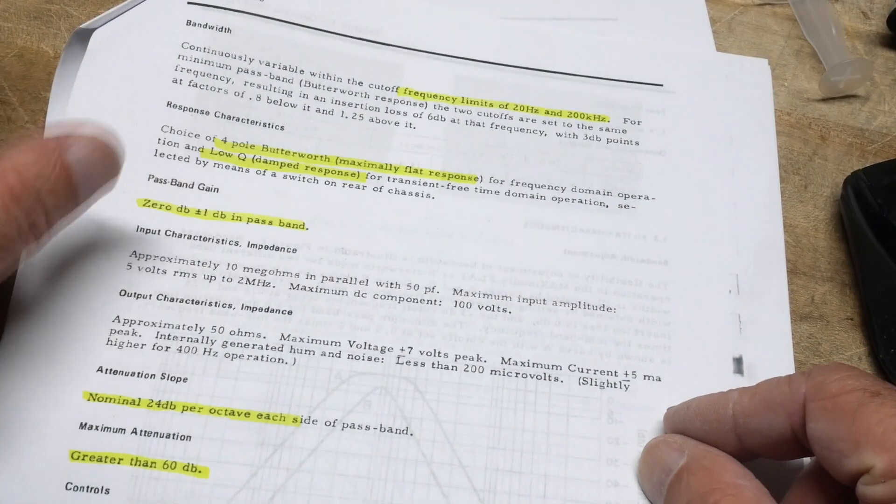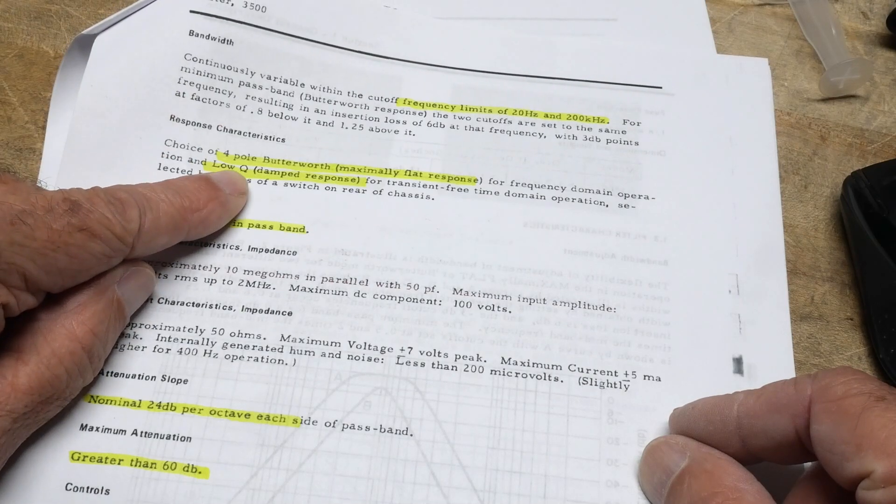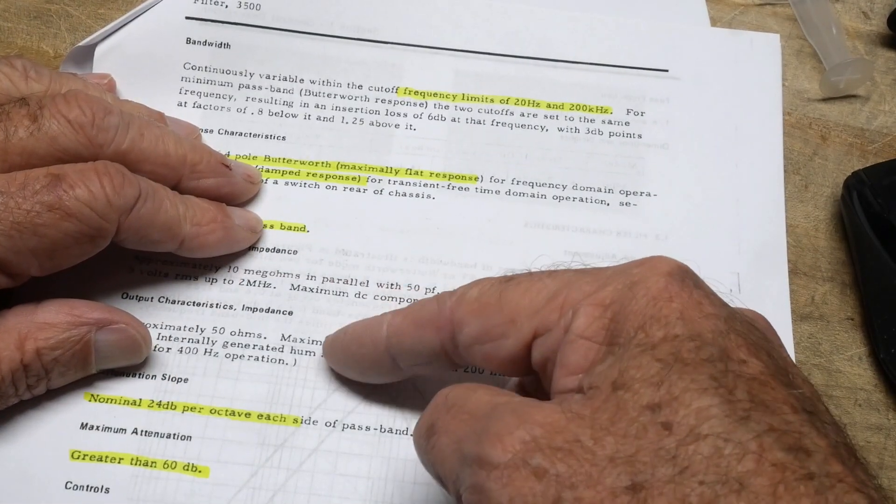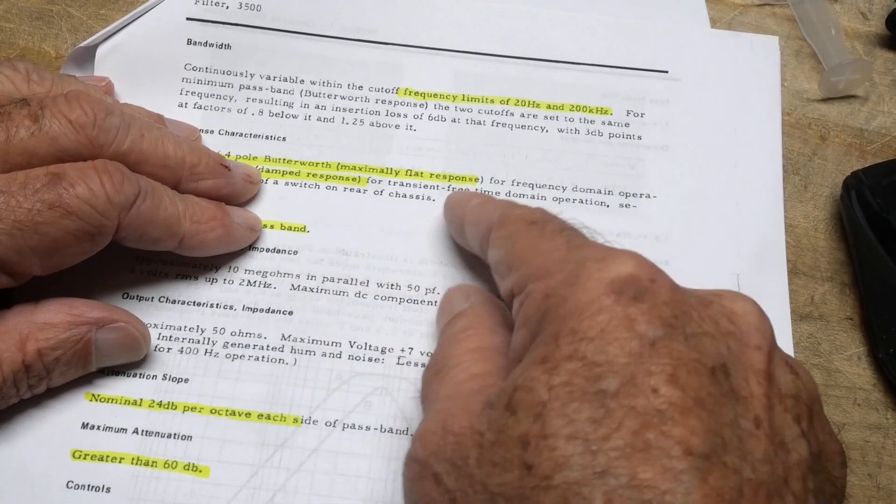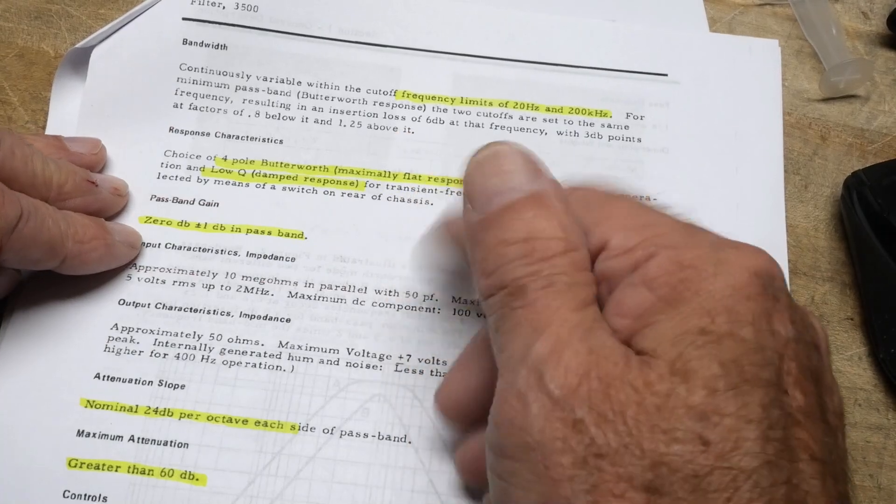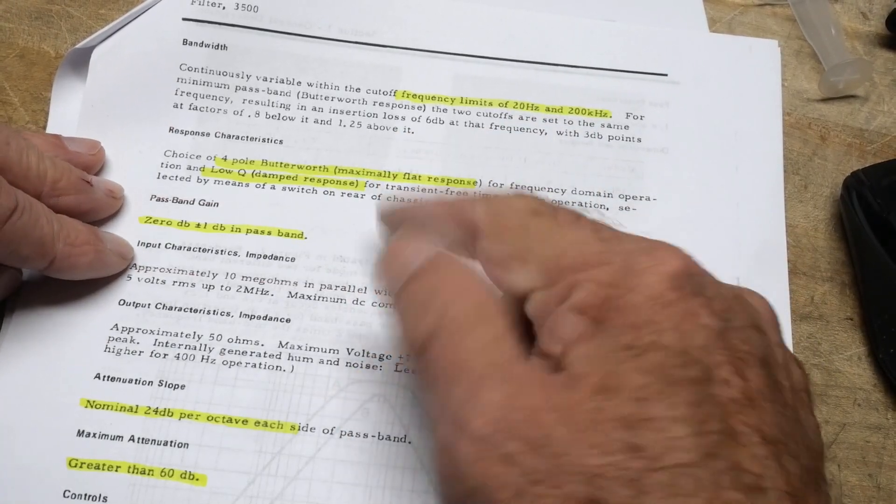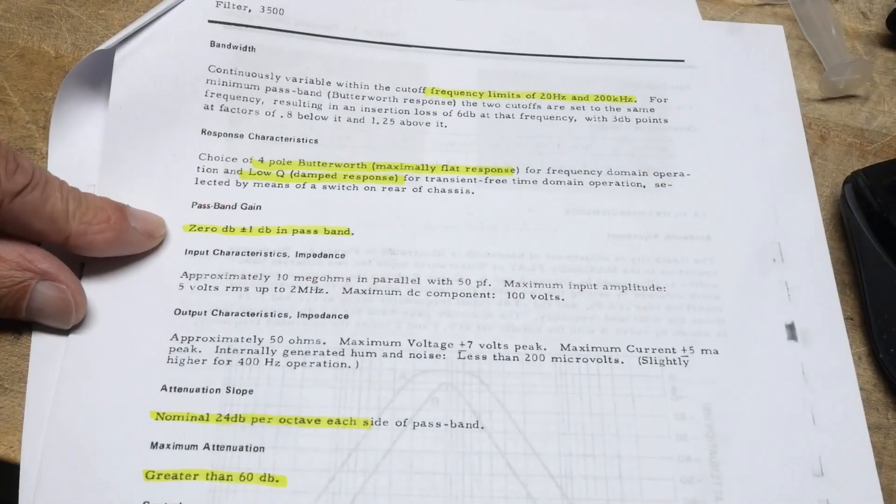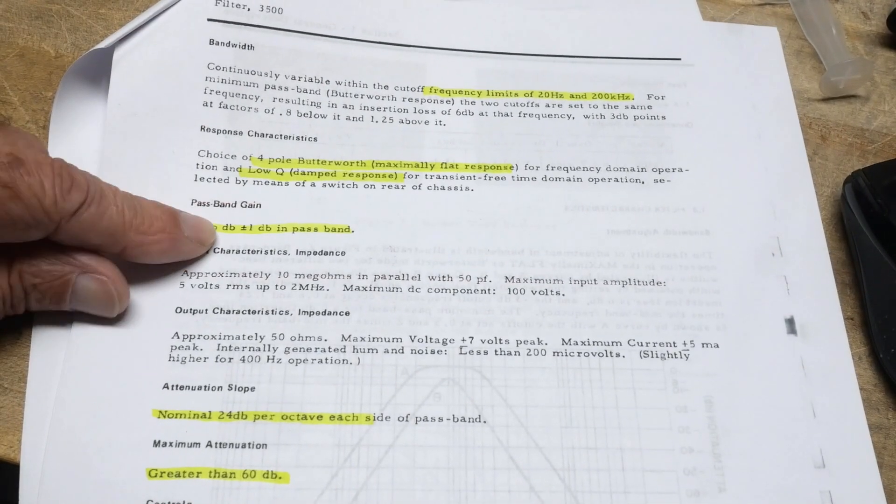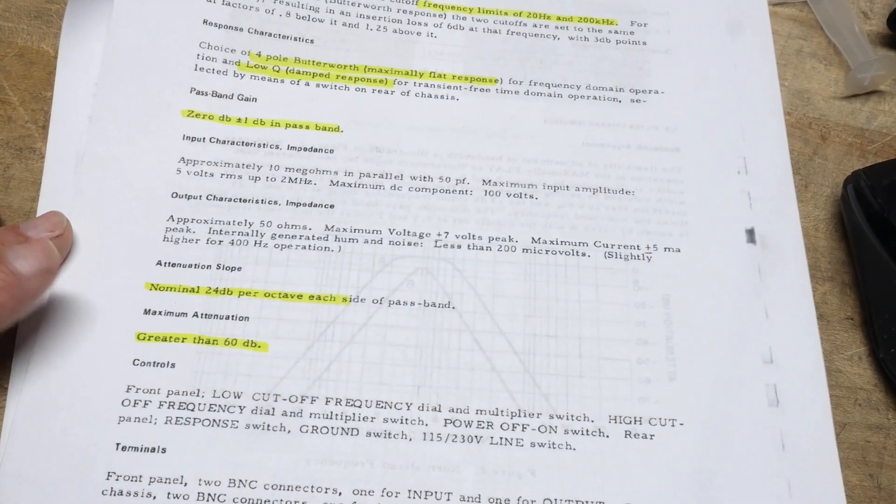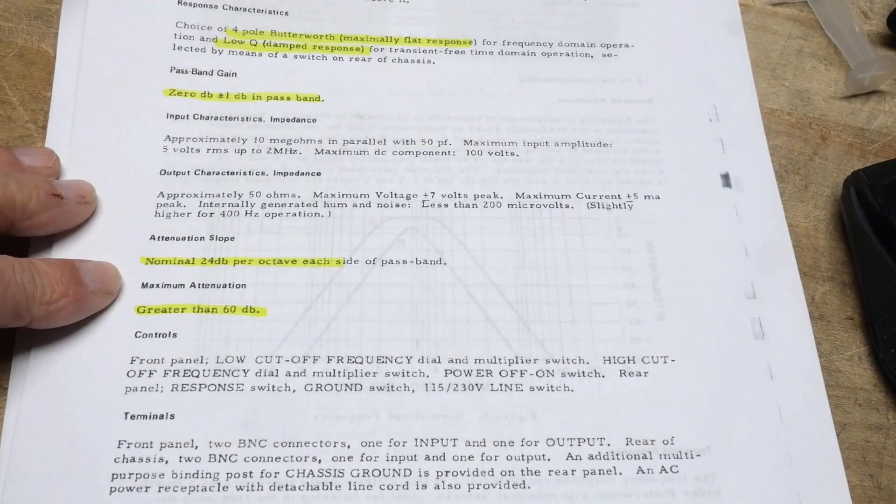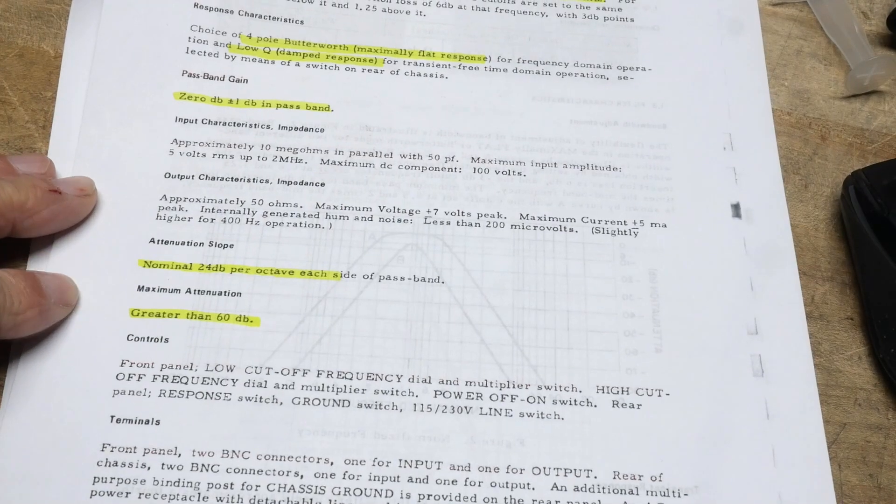This one also has a switch in the back that says low Q. If you see your signal ringing on a transient, you can flip that switch and it rounds that off a bit. It won't make the response as sharp, but it'll roll off any edges. It is plus or minus 1 dB of ripple, maximum 24 dB per octave slope, and attenuation greater than 60 dB.